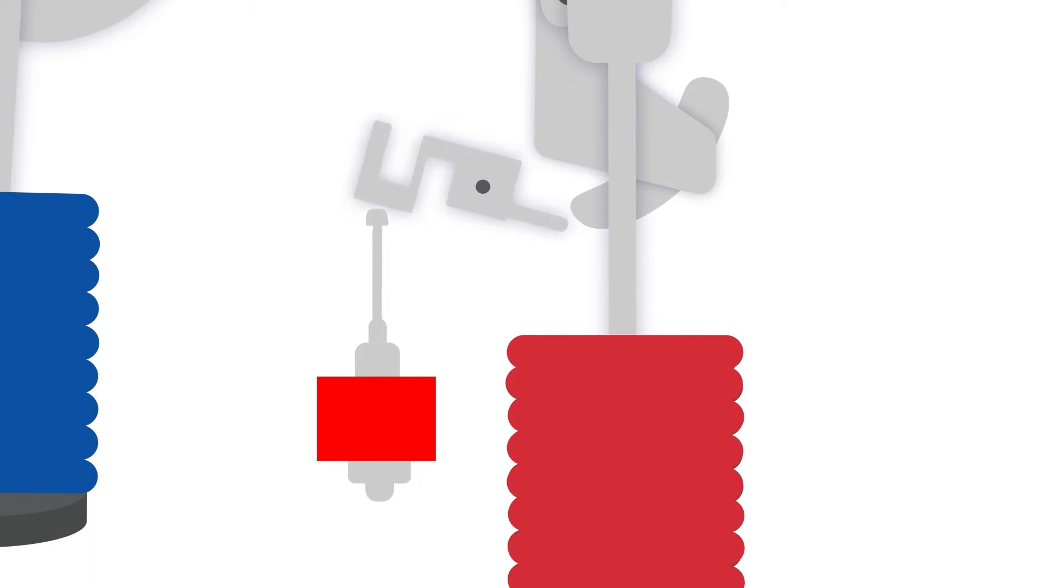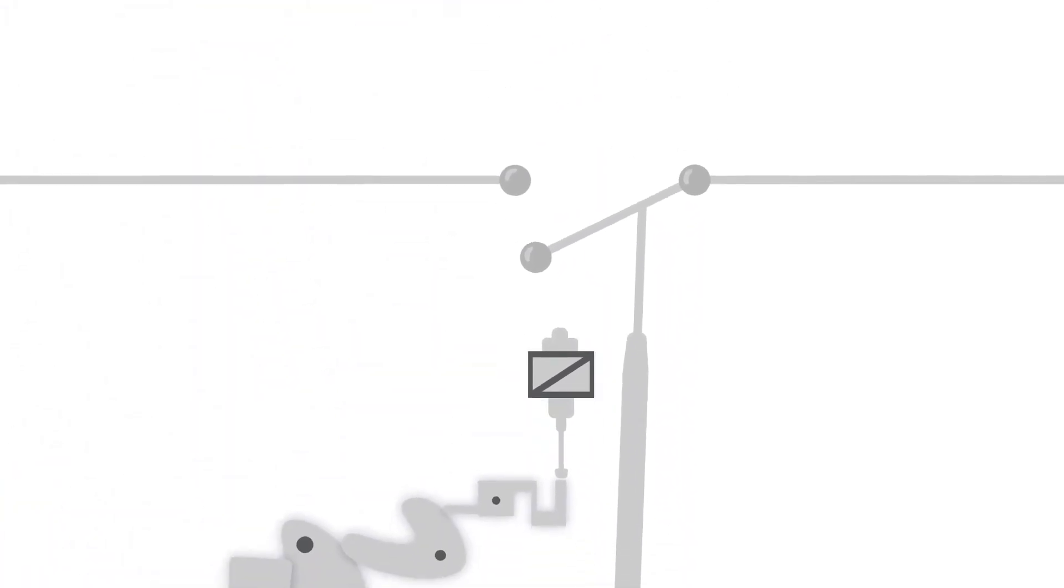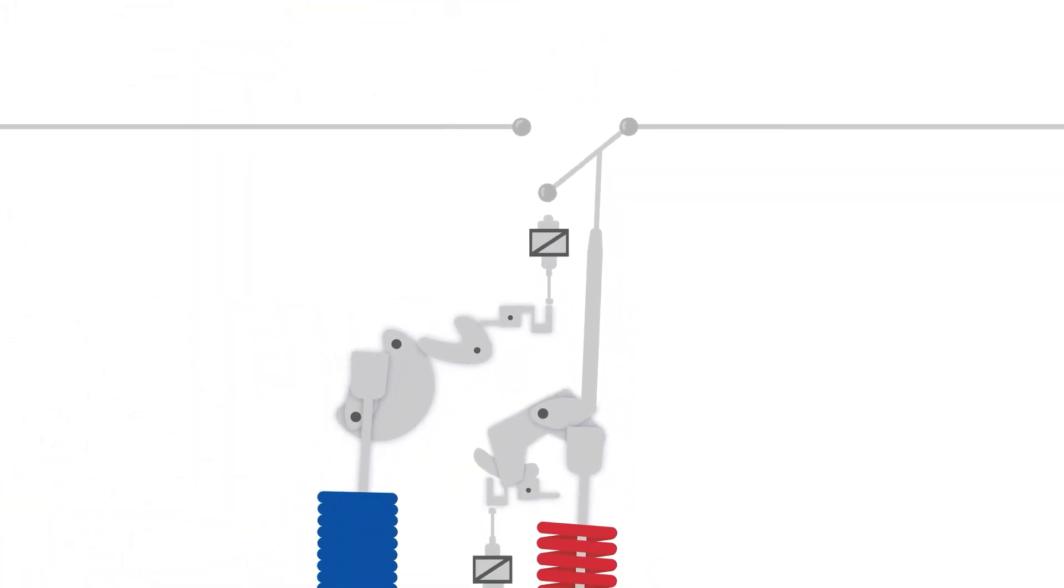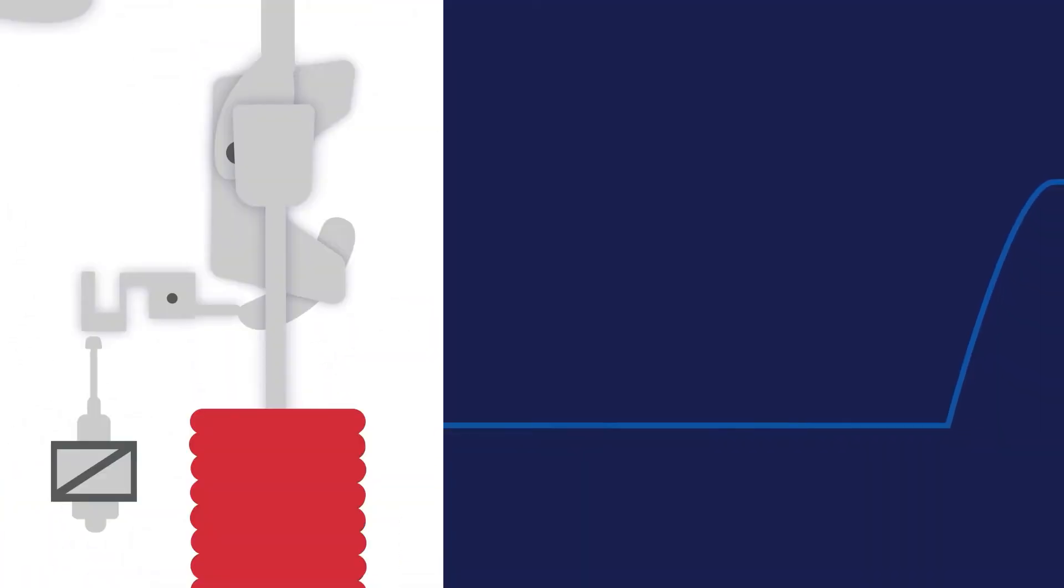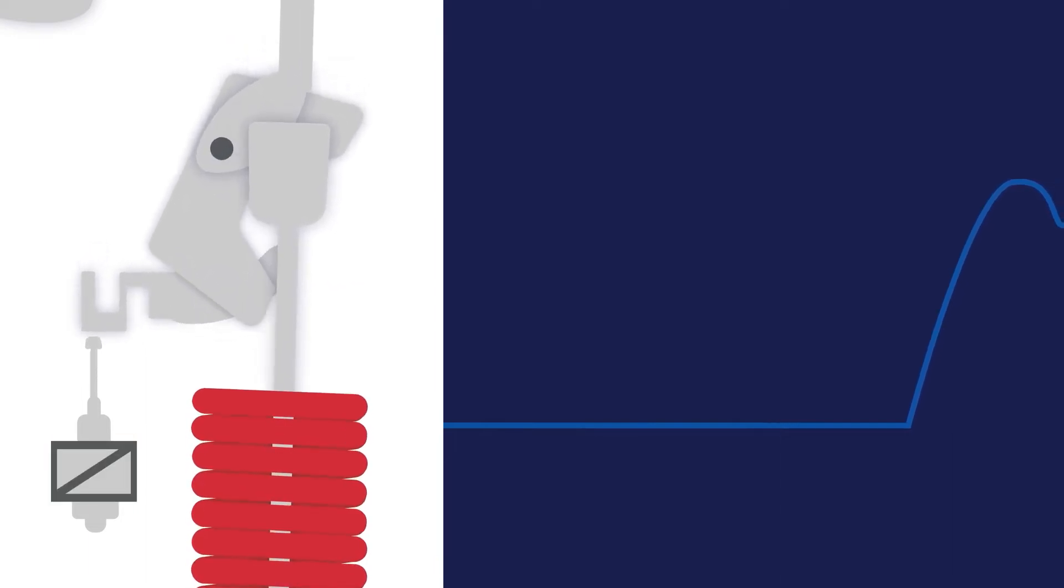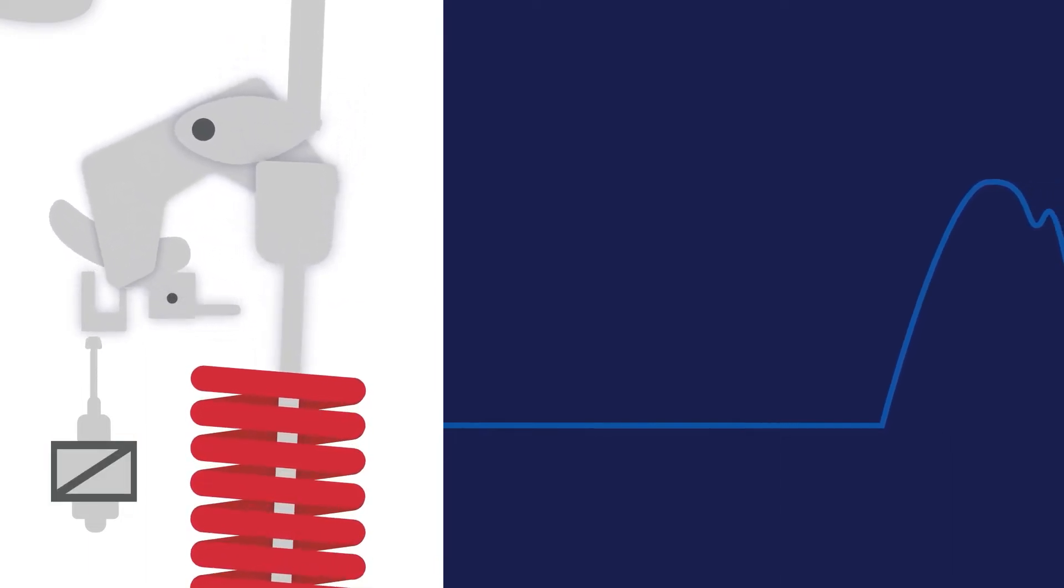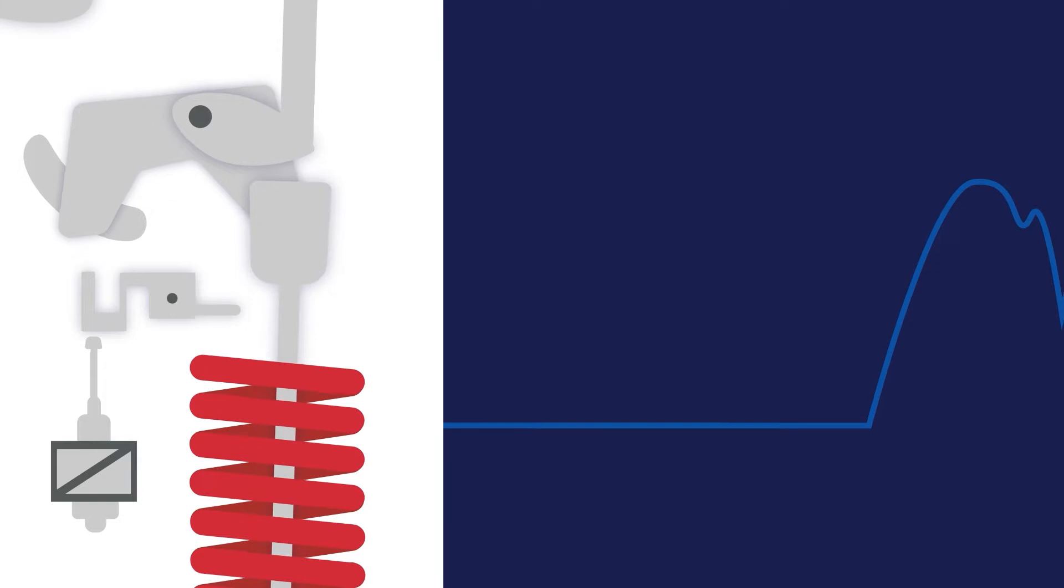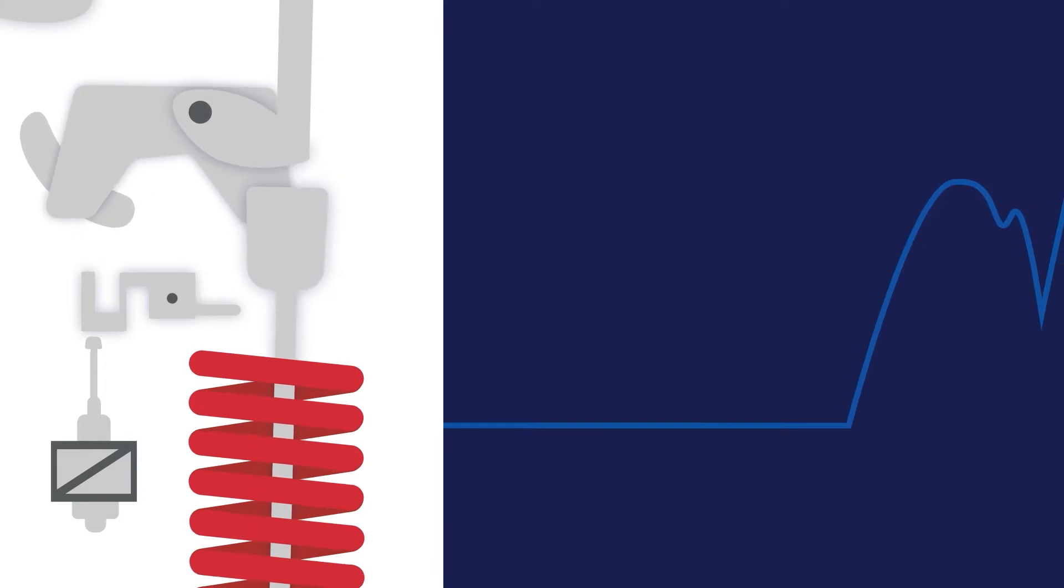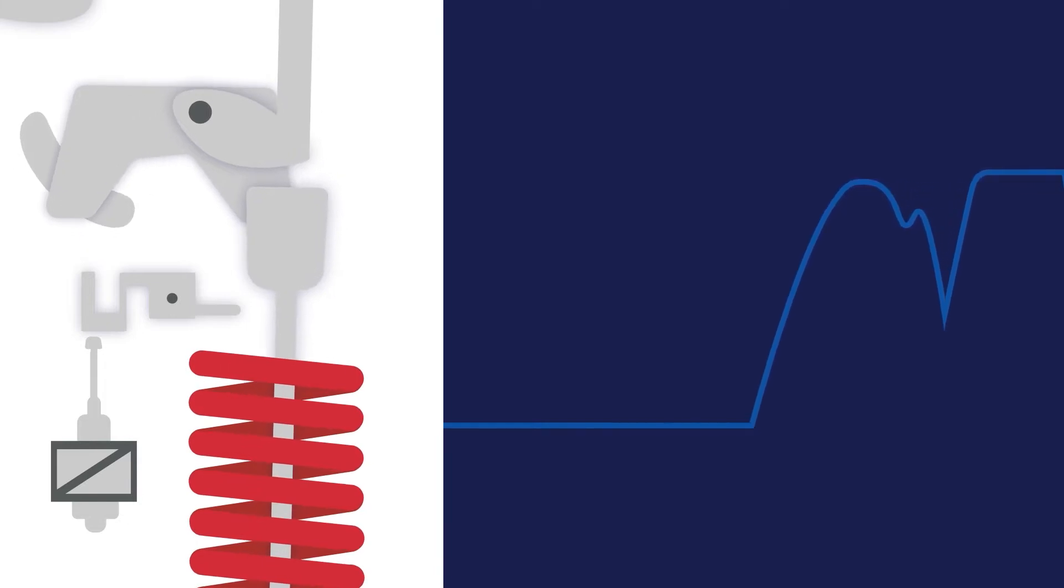This decrease will continue until the plunger strikes the latch, releasing stored energy, allowing the switchgear to begin to open. This is visible in the waveform capture as a momentary dip in current immediately followed by the current continuing its upward trend. At this point, the plunger strikes a buffer and begins to rise until maximum current is achieved.